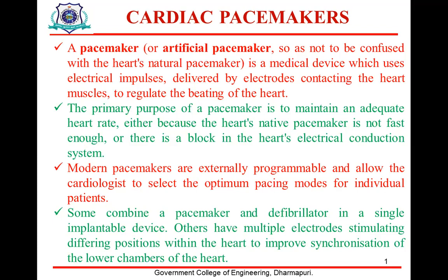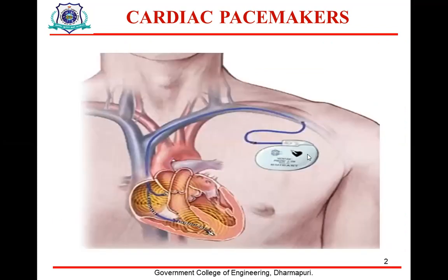The primary purpose of the pacemaker is to maintain an adequate heart rate, either because the heart's native pacemaker is not fast enough, or because there is a block in the heart's electrical conduction system. Modern pacemakers are externally programmable and allow the cardiologist to select the optimum pacing modes for individual patients. Some combine a pacemaker and defibrillator in a single implantable device. Others have multiple electrodes stimulating differing positions within the heart to improve synchronization of the lower chambers. So this is the cardiac pacemaker. It will be placed in the heart.